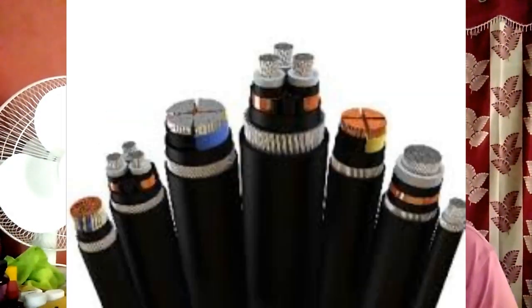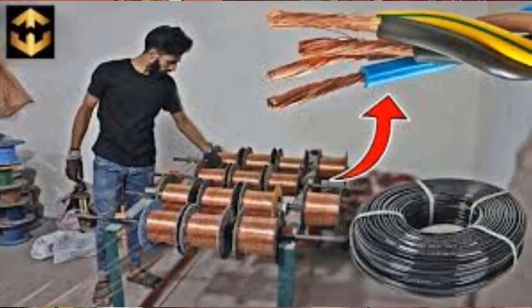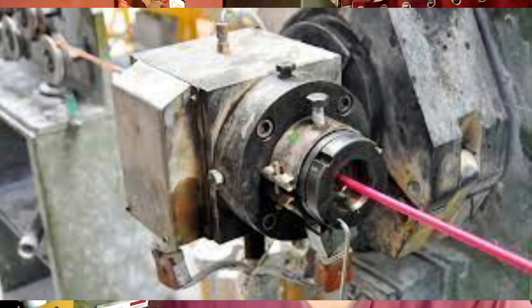And next point, the final step, is testing. Cables undergo the following tests: conductor resistance test, thickness of thermoplastic and elastomeric insulation and sheath, tensile strength and elongation at break of thermoplastic and elastomeric insulation and sheath, thermal aging in the air, shrinkage test, ozone resistance test, heat shock test, hot deformation test, bleeding test, cold impact test, water absorption test, environmental stress cracking test. These are the tests required.